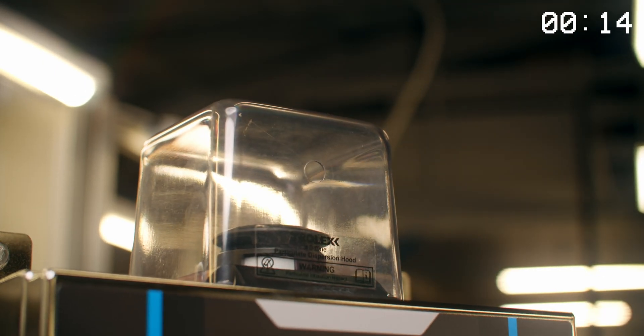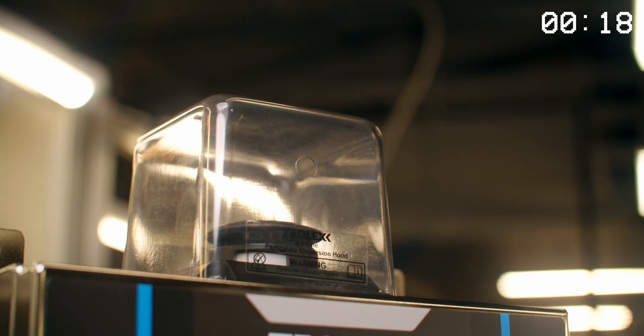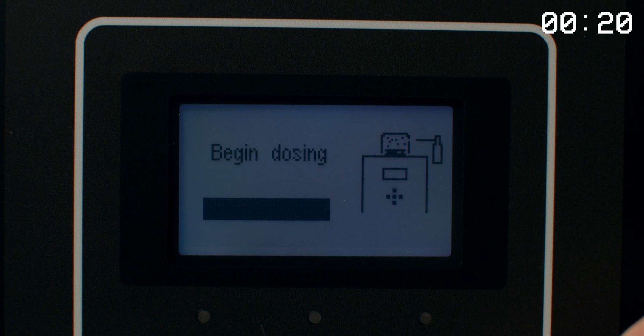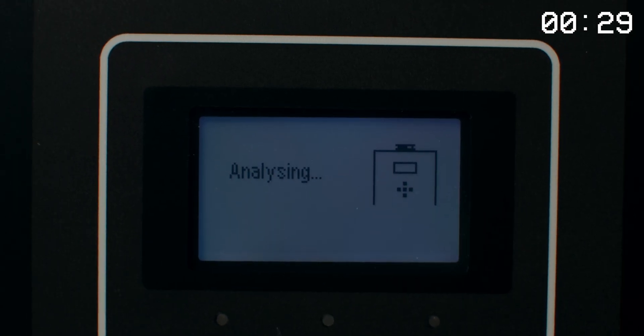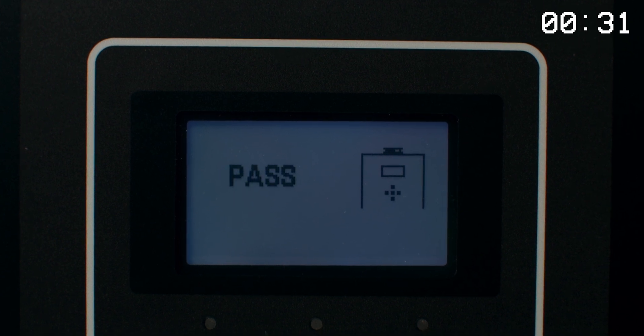Place the hood over the particulate inlet and then insert the nozzle of the sample bottle into the hood and give it a good few doses of reference material. And it's a pass!